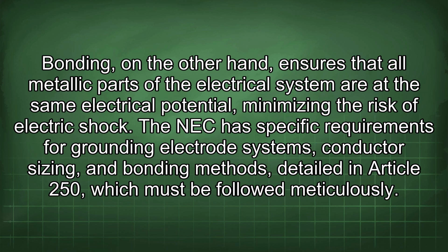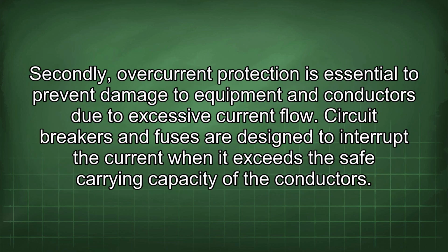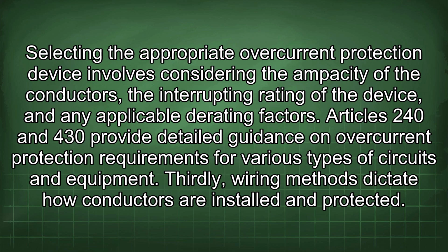The NEC has specific requirements for grounding electrode systems, conductor sizing, and bonding methods, detailed in Article 250, which must be followed meticulously. Secondly, overcurrent protection is essential to prevent damage to equipment and conductors due to excessive current flow. Circuit breakers and fuses are designed to interrupt the current when it exceeds the safe carrying capacity of the conductors. Selecting the appropriate overcurrent protection device involves considering the ampacity of the conductors, the interrupting rating of the device, and any applicable derating factors. Articles 240 and 430 provide detailed guidance on overcurrent protection requirements for various types of circuits and equipment.